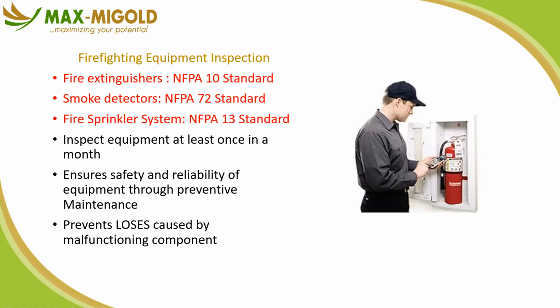But if you lay them up in layers, that's what we call parallel. Instead of having one 25 kg of DCP, you now have 4 numbers of 6 kg cylinders placed in 4 different places. That's 6 times 4, which is 24 - so it's as good as having 25 kg of DCP.